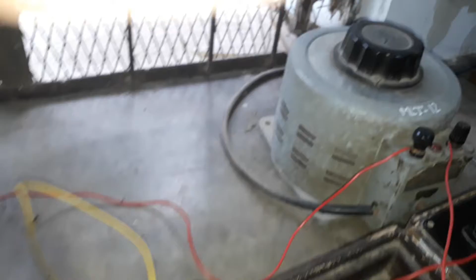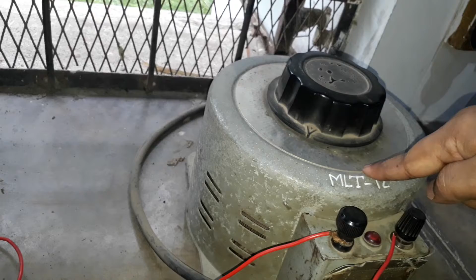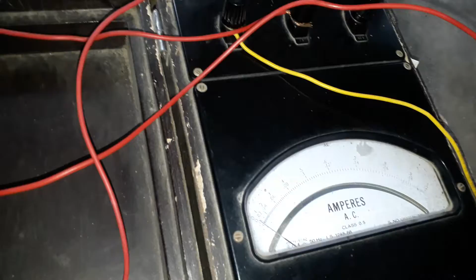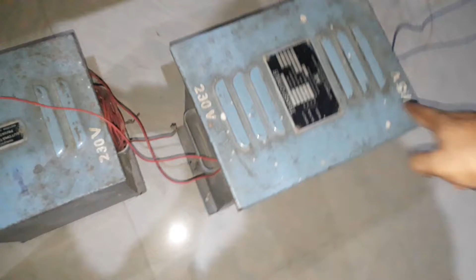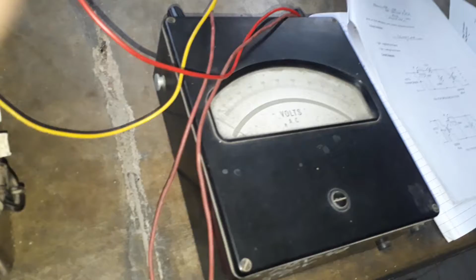Now let me quickly go through the various equipment you see on your test bench. The first one you see here—you are already aware of this equipment—this is your auto transformer. Then from the auto transformer we come to the wattmeter, this is your ammeter, this is your voltmeter, and here on the floor you see this 230 by 115 volt unit. This is our single phase transformer on which we are going to perform the open circuit and short circuit tests.